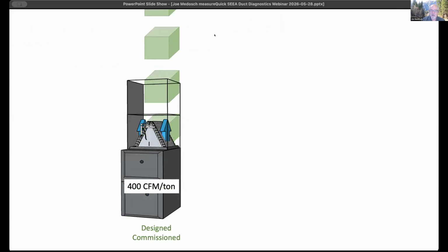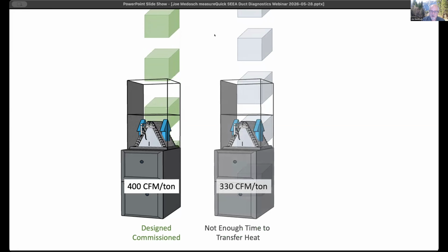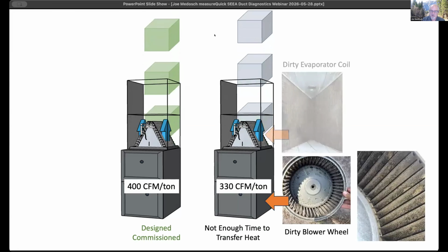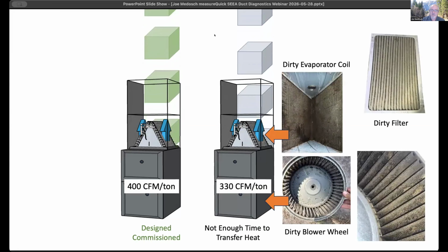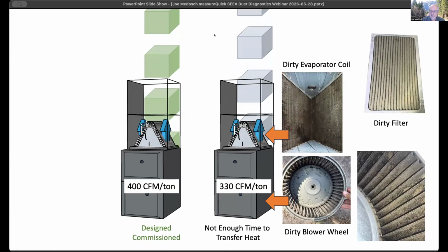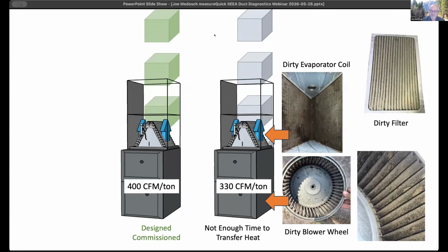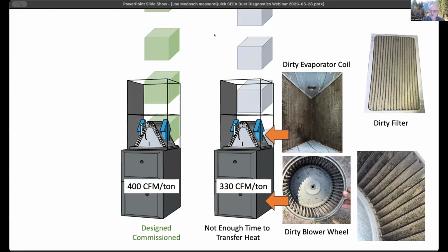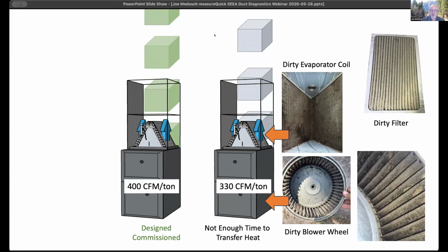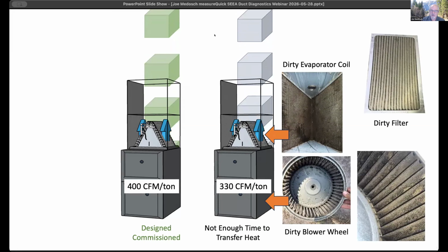I tried to visualize this, to see if we could explain it. Maybe you designed and commissioned a 400 CFM unit, and then you come back later and find out, and we'll just say I haven't measured it yet, but I sense there may be an airflow problem. And when I did measure it, I found out there's only 330 CFM, and people are failing to inspect these conditions before they're checking refrigerant charge.